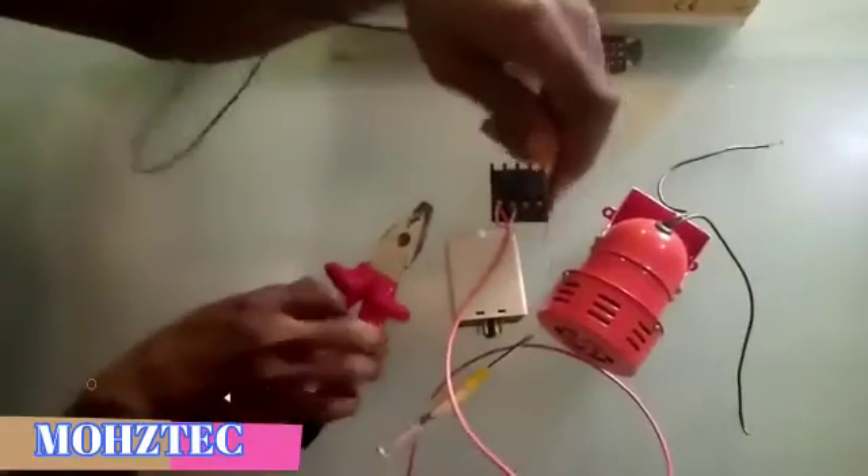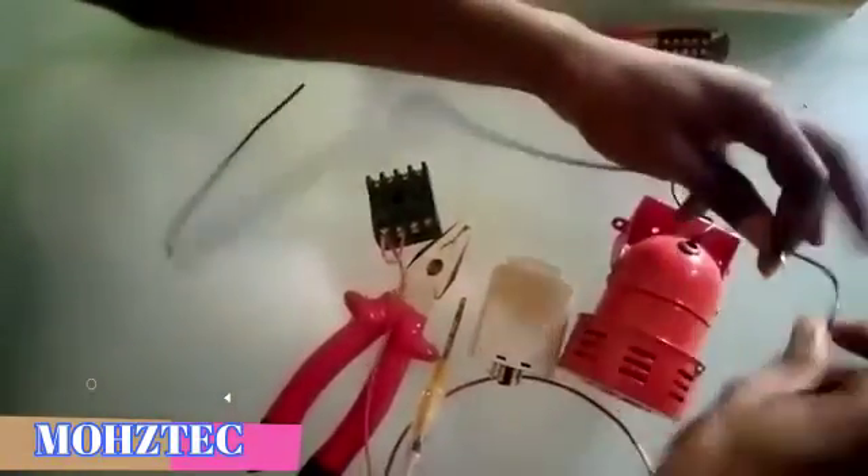I've connected the live to pin 7 and looped from pin 7 to pin 8. Now let's go to the neutral cable — this black cable. The neutral cable will be going to pin 2. This siren also has a neutral cable; from the middle it shows AC 220 volts, meaning either wire can serve as neutral — it's not polarity-specific.